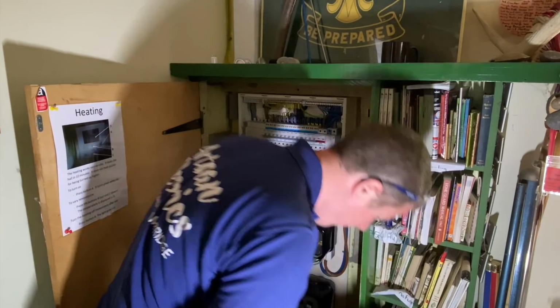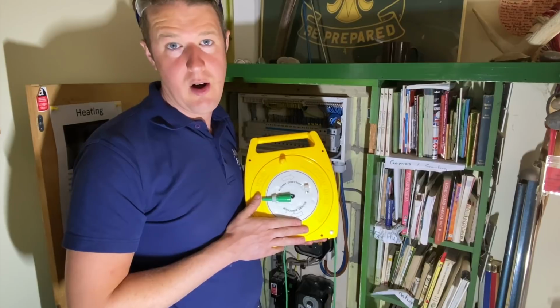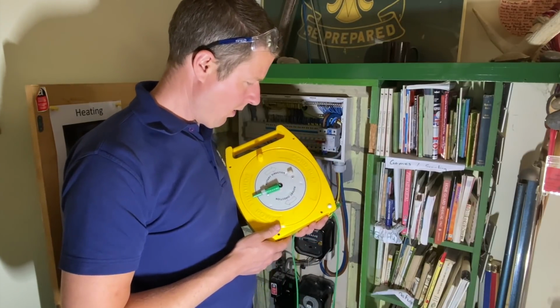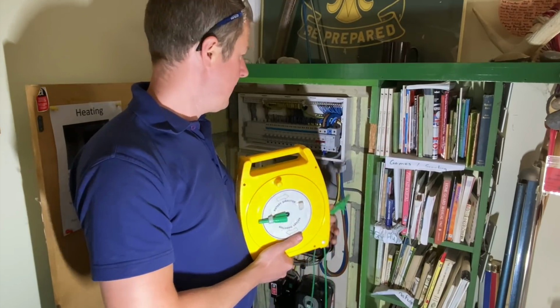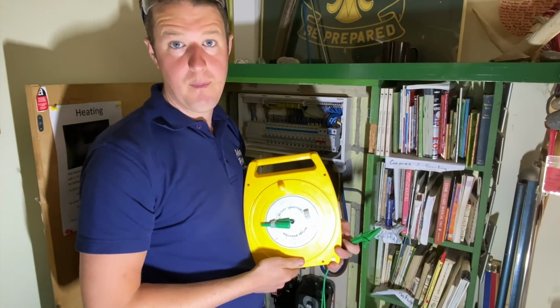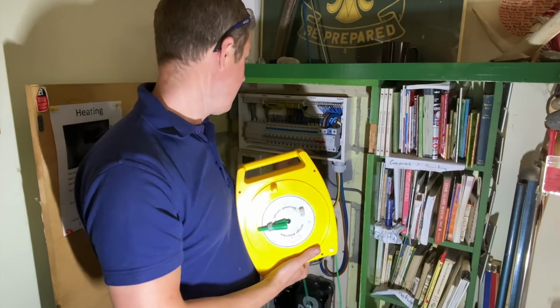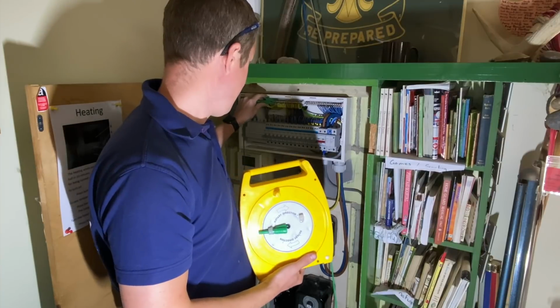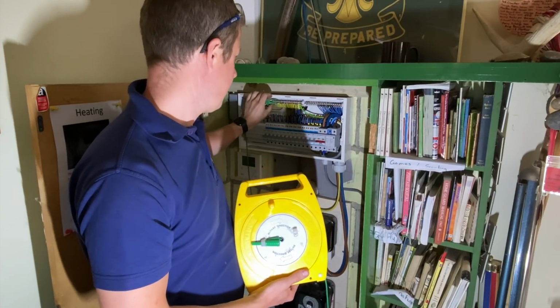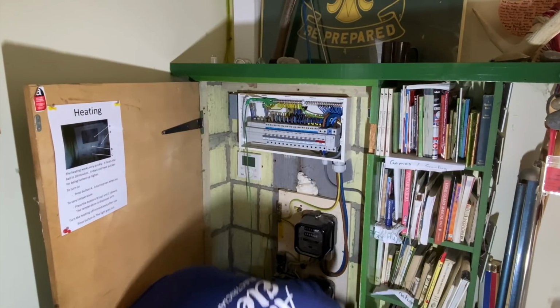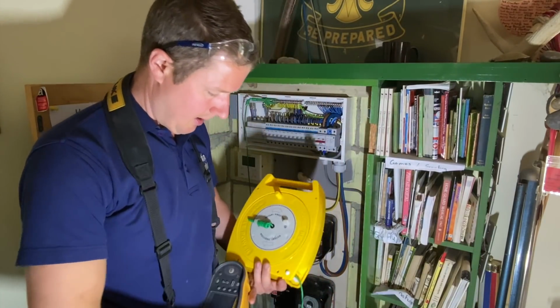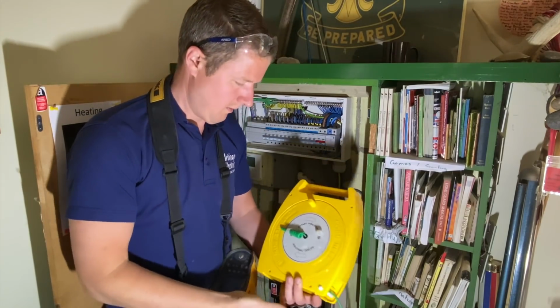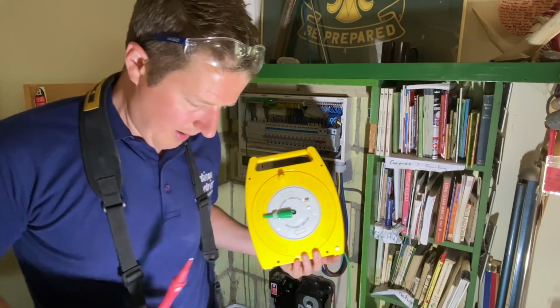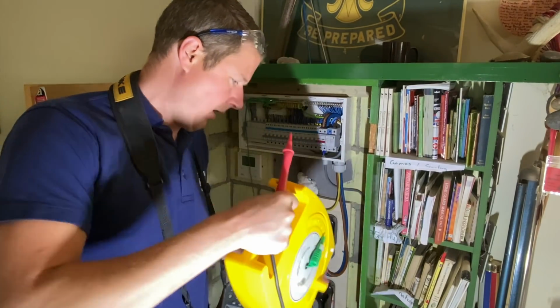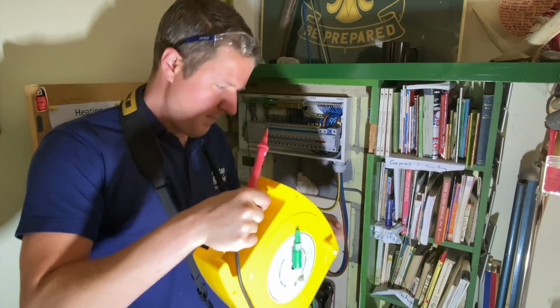And to do this, what I usually do is use one of these, which is what we call a long wander lead, or an R2 lead, and it's basically a 50-meter long lead which you can then use to connect and test at all the various furthest points. You test the exposed metalwork. So basically the crocodile clip here is clipped onto the earth terminal at the consumer unit. The other end of this is connected to my tester. I usually reel out a bit of slack first so that you don't have to keep disconnecting it every time.